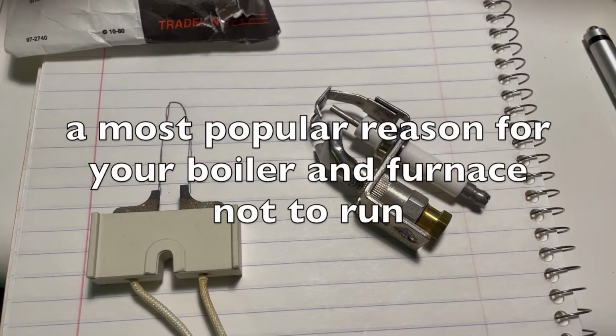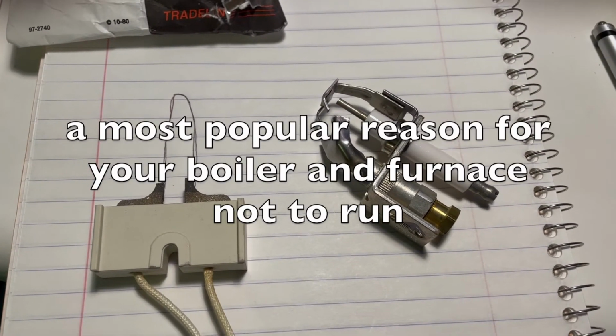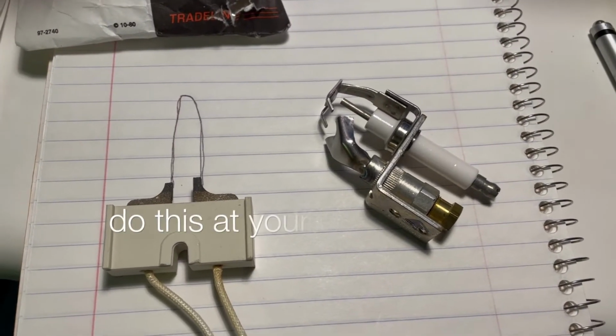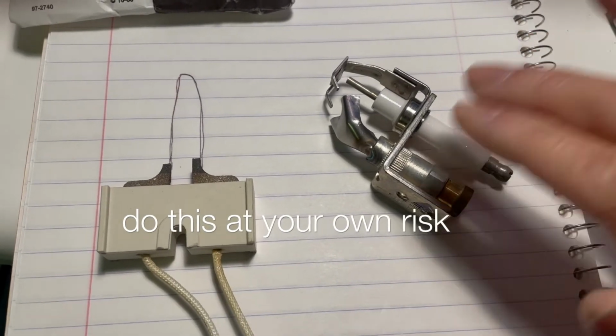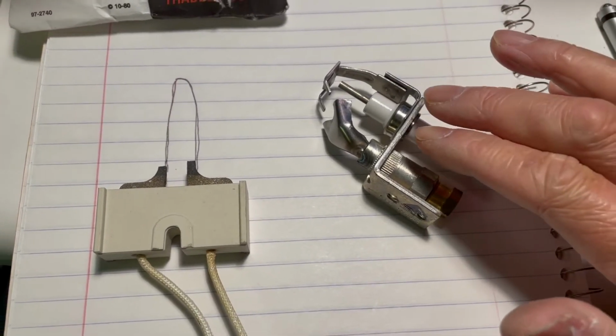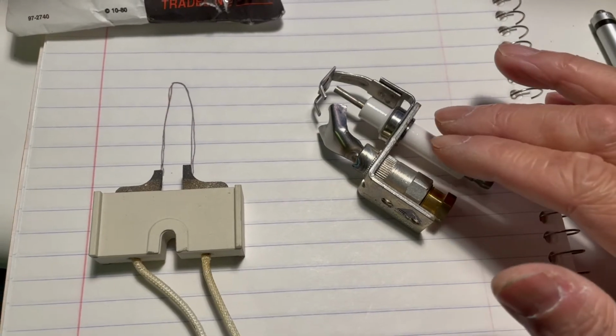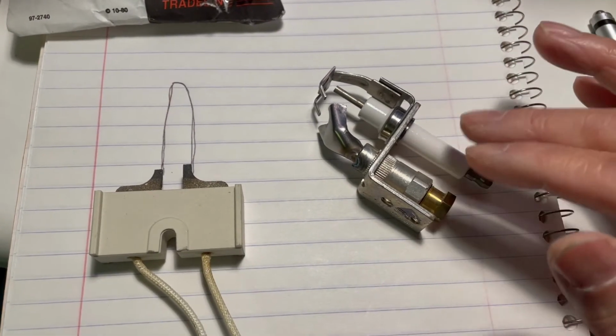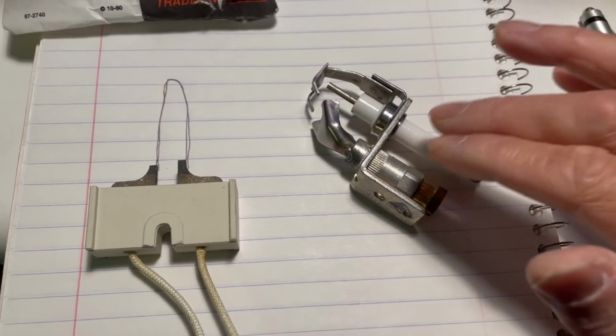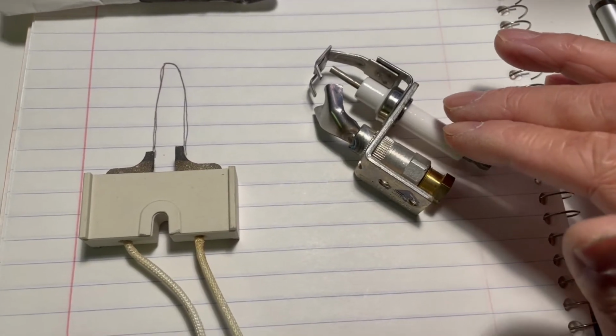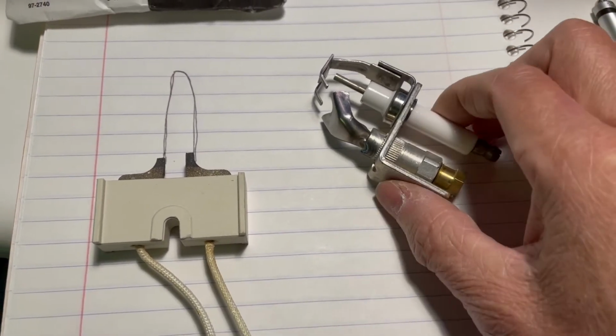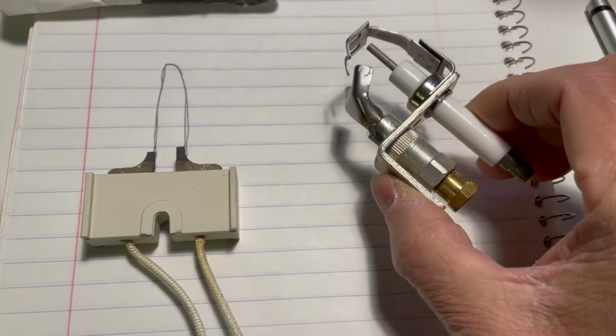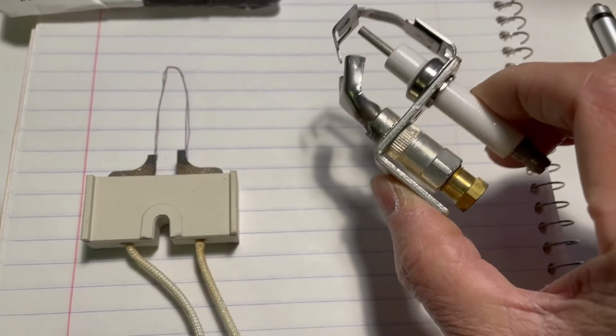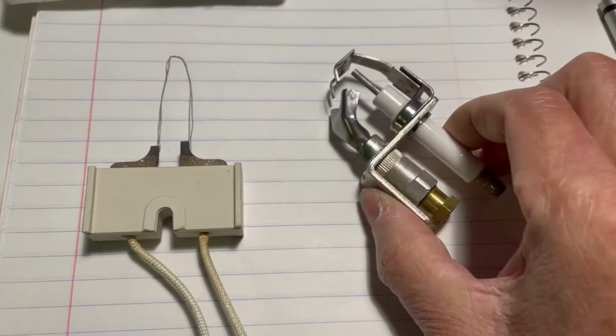So if you have a boiler or furnace long enough, sooner or later you'll run into this problem here, which is the most common problem for your furnace or boiler not working, and it is the ignition. In this case, this one here is a combination flame sensor and igniter.